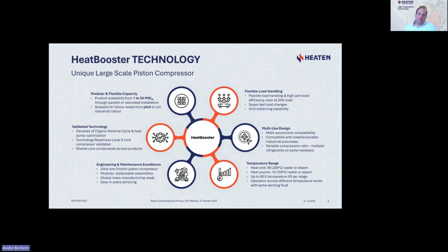What is important and what I would like to highlight on the heat booster technology is the piston compressor technology, because we are convinced that flexibility is also key for the market. So we can go down to 20% of the nominal load with the same efficiency, and 30, 40, 50% even with a higher efficiency at that load.